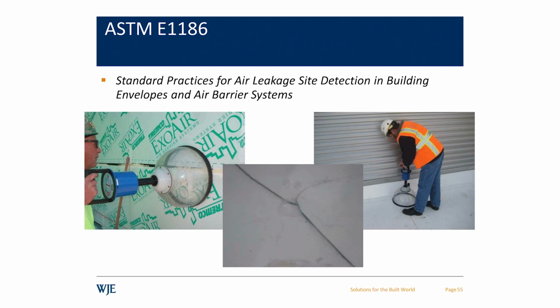Another way that we do this throughout construction is the bubble gun test. I don't know if any of you have seen that, but with an air barrier, you put a soapy solution on the air barrier surface at seams or at penetrations, so cladding penetrations, and then you have this clear dome that has a vacuum pressure, and if a bubble forms through the soapy solution, it's a site for air leakage. And the thing to remember about that, like I said, it's a qualitative result. You're not looking for an air leakage rate. So that is important to remember.